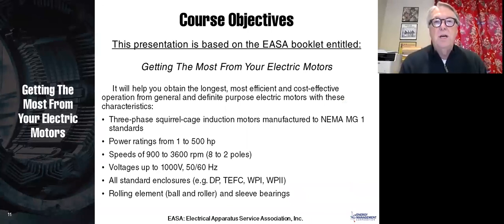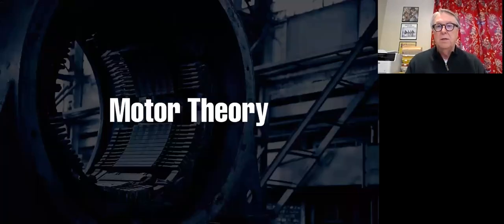All right, these are our course objectives, and this is on the front of the booklet, which you will download, hopefully. This is one of those great booklets to download, put in your files, and refer to periodically. We're going to be addressing primarily NEMA frame motors from 1 to 500 horsepower in this presentation, and from 900 to 3,600 RPM, and voltages up to 1,000. Now, that doesn't mean that we're not going to talk about other motors a little bit as well, but the EASA booklet is based on those motors, and since larger motors tend to be very specialized and require a lot of specialized education, and a lot of manufacturer guidance, we're going to concentrate on the NEMA sizes, but we'll also talk about some of the larger motors as well.